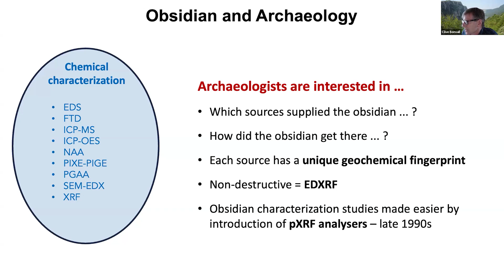Now, anybody involved in this type of research needs some way of checking the results that are produced by the instrument and of calibrating the instrument. Well, there are two ways to do that. One is to use a dedicated obsidian calibration set like Ellery Fram's Peabody Yale reference obsidians. So these are 35 obsidians from different parts of the world, each one chemically distinct. Ellery Fram has had these analyzed by high-end techniques like neutron activation and ICP-MS, and so we know the chemical compositions of all these obsidian reference standards. It's simply a matter of taking measurements on these with a portable XRF analyzer, and the one I use is an Olympus Vanta M, and then comparing the results against the known values.